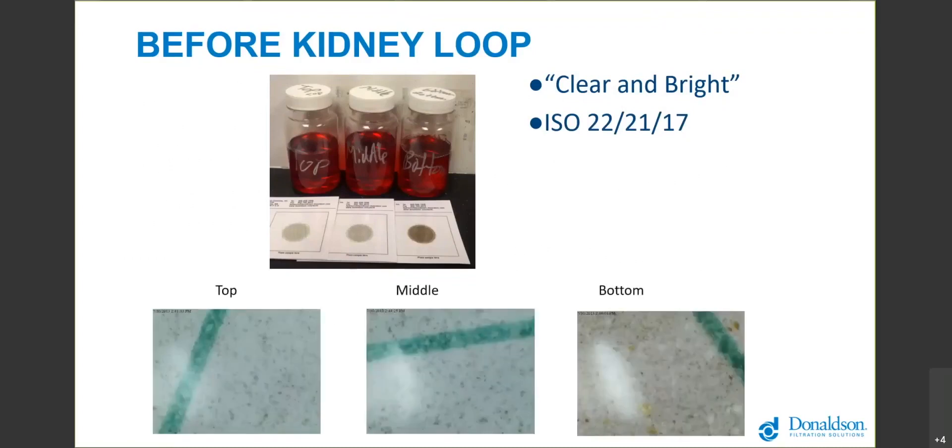We took patch tests of those fuel samples, so we put them onto a filter patch and then evaluated under a microscope. This is about 125 times magnification and you can see there's a lot of debris in there. That green line on this patch represents about a hundred microns in diameter.